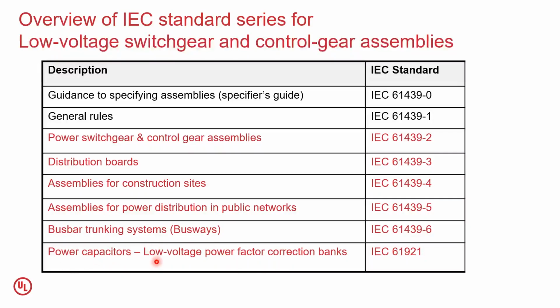Then you have the power factor correction banks. All these standards in one way or the other have some general requirements. When I say general requirements, it could be the rated voltage, the rated current, the frequency, the impulse voltage, the clearance and creepage values, or some of the construction similarities, because they're all electrical equipment, they're all assemblies of low voltage switchgear and control gear components. What the IEC did was, they tried to group all the common requirements into one common standard called 61439-1. However, you need to note, we can't certify a product to 61439-1 because it is not a product standard.